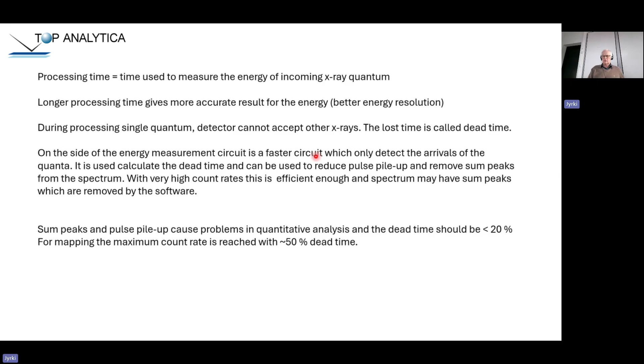And therefore the manufacturers are also using corrections in the software which are removing these sum peaks. However, these sum peaks can be problematic in quantitative analysis, and the user should select settings where the dead time is less than 20%. If you would like to have a very fast mapping, then you can increase the count rate to close to 50% dead time.